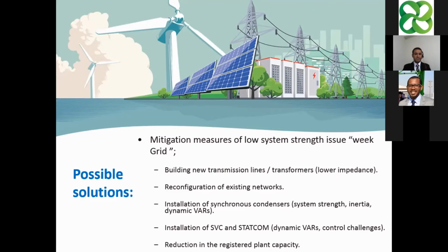The possible solutions and mitigation measures for the low system strength issue: we can build new transmission lines and transformers with lower impedance values. We can reconfigure our network. We can install synchronous condensers, which help increase system strength and also provide inertia and dynamic voltage regulation. We can install static VAR compensators and STATCOMs, which enhance dynamic voltage regulation as well as control challenges.